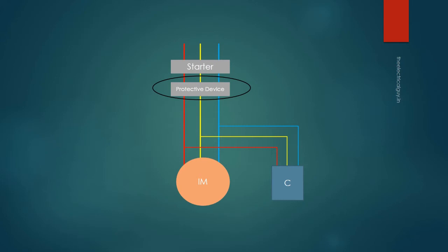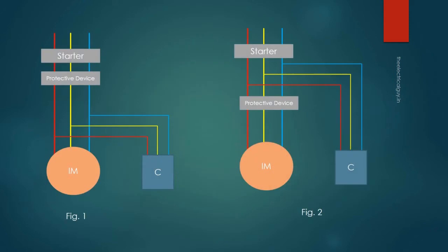This type of correction is generally used for induction motors and fluorescent lamps. In case of direct connection as shown in figures 1 and 2, there is a risk that the motor keeps running even after the disconnection from the supply because of the residual kinetic energy.